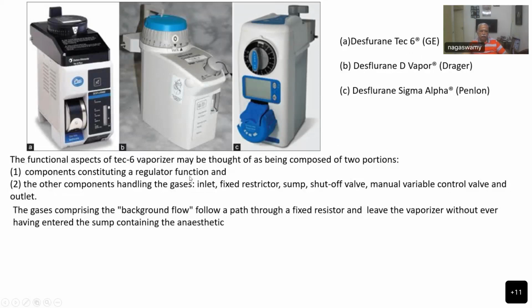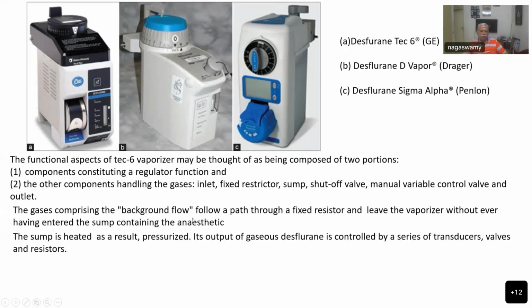The components constituting a regulator function and the other components handling the gases, that is inlet, fixed restrictor, sump shut-off valve, manual variable control valve, and outlet. The gases comprising the background flow follow a path through a fixed resistor and leave the vaporizer without ever having to enter the sump containing the anesthetic. This is a very, very important thing. And the sump is heated as a result.